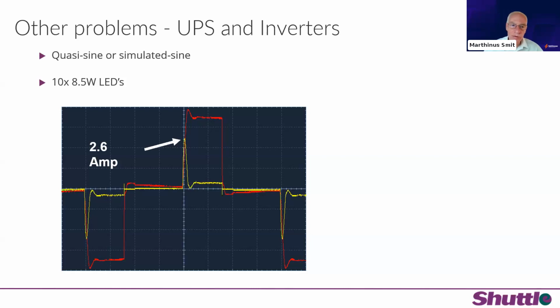So once again, measured waveforms. This is just to show why you must never use a quasi-sine or simulated sine wave, especially on dimming, and in my opinion on LEDs as well. This is a measured waveform of a quasi-sine wave UPS, which is available in the market, and you can see that it's actually not even a sine wave. It's a block wave. And the red waveform here, you can see the peak voltage reaches close to 400 volt. And with only 85 watts of LEDs, you can see that there's a 2.6 amp inrush current into the UPS.